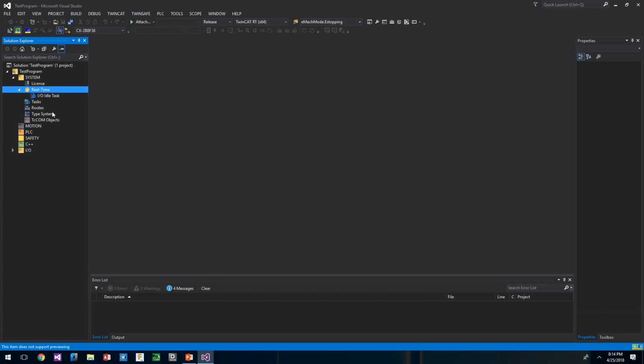What that does is run the CPU at 100%, running the PLC program all the time, and as soon as it gets done scanning the PLC program, it immediately starts again, in a continuous loop. TwinCAT is a little bit different. It's much more deterministic, and that can be a good and a bad thing. It's mainly a good thing. It's really nice to know exactly what your scan time is going to be rather than just guessing, and, hey, the scan hits whenever it hits.